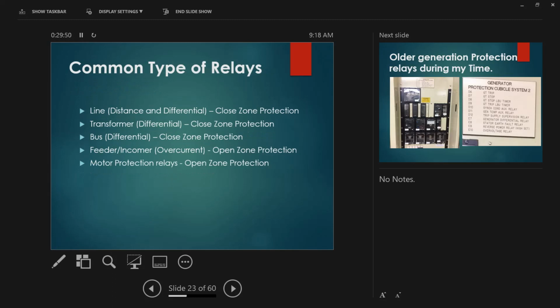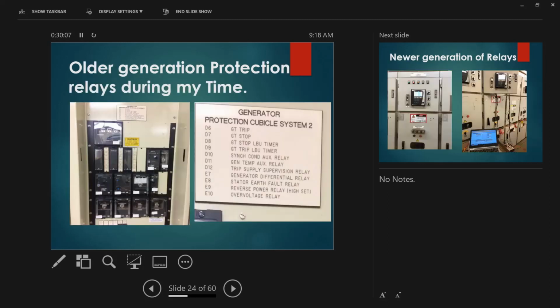Line differential is closed zone, transformer, of course. Feeder overcurrent or motor relay, that will be open zone because it can look to the longer cable going to the last point of energized cable anyway. If there's some short there, the feeder can pick that up at some point. Now, older generation protection relay. This is what I'm saying.